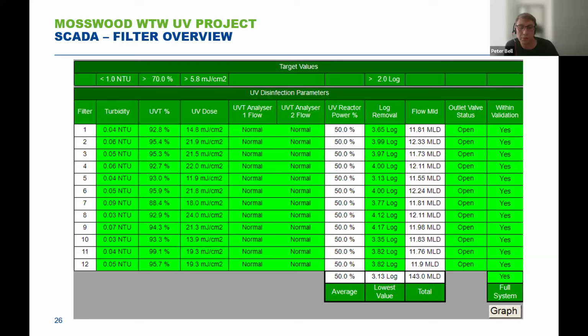So for that UV reactor power, we set a minimum to run at 50%, but what we could do with this is we can see if the UV reactor power is climbing. We can say that we maintain our minimum dose, but the UV reactor power is climbing. We can then start to delve into why that is starting to climb. That could be because the quartz sleeves are fouling, so we could get an indication that the wiper isn't doing the job that it's meant to be doing. It could also be an indication that the transmittivity of the water is reducing.